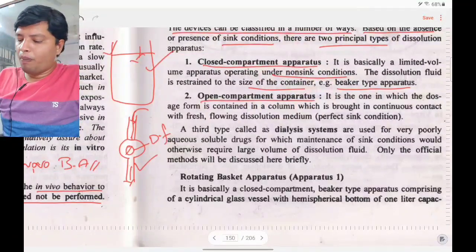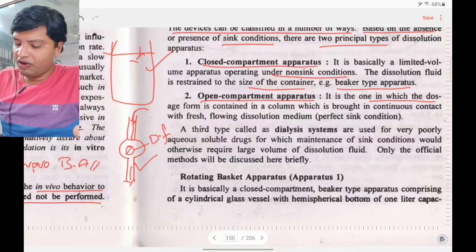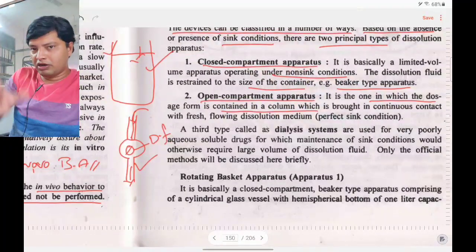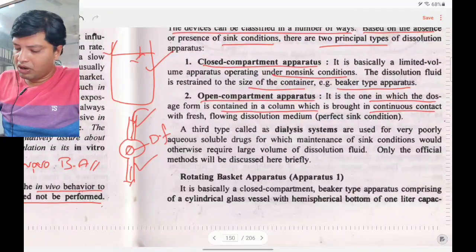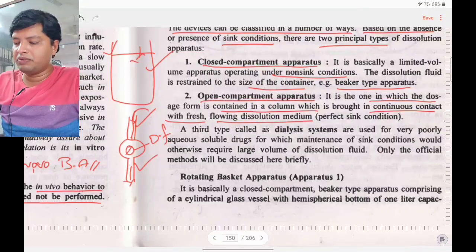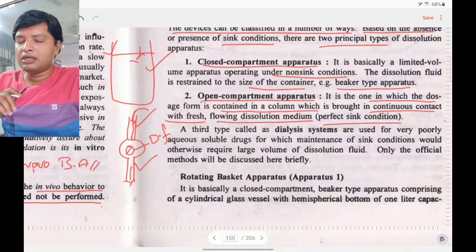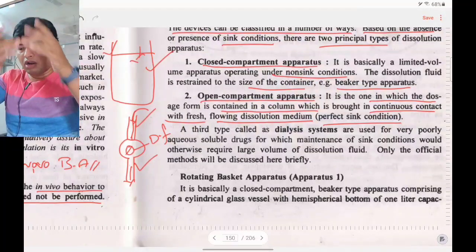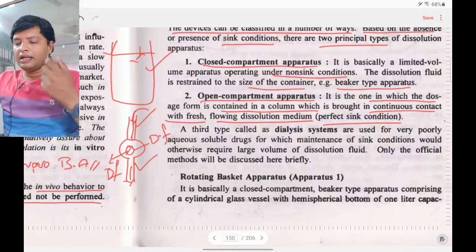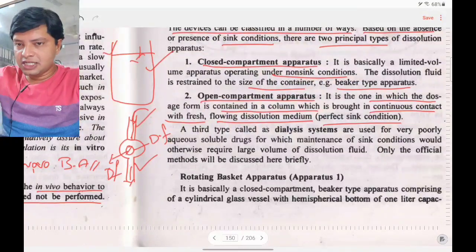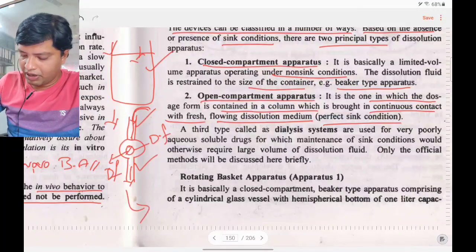The open compartment apparatus contains the dosage form in a column, brought into continuous contact with fresh flowing dissolution medium, maintaining perfect sink conditions. Fresh dissolution medium flows in, passes through the dosage form, and exits — this is the flow-through cell.